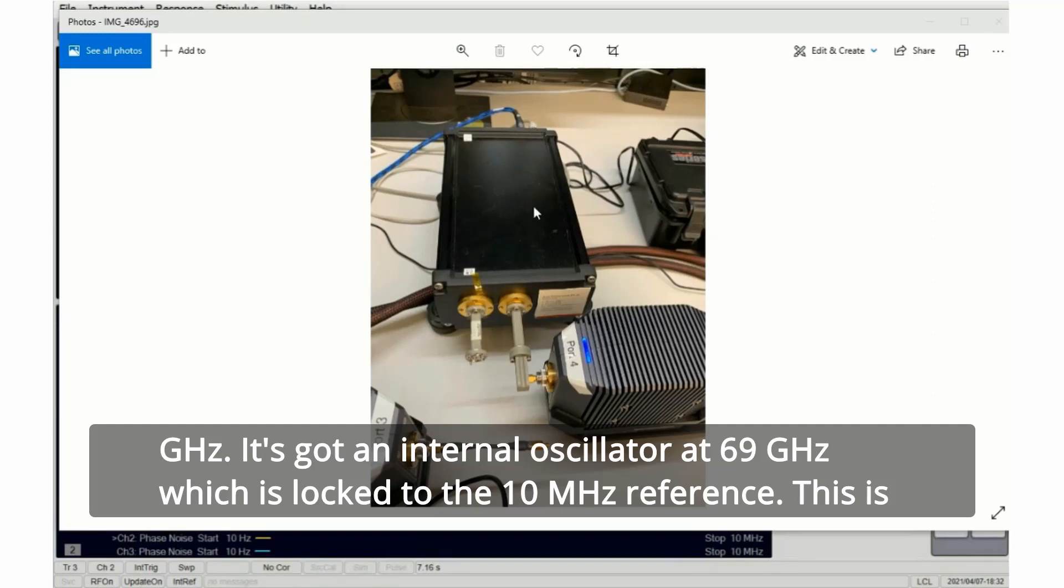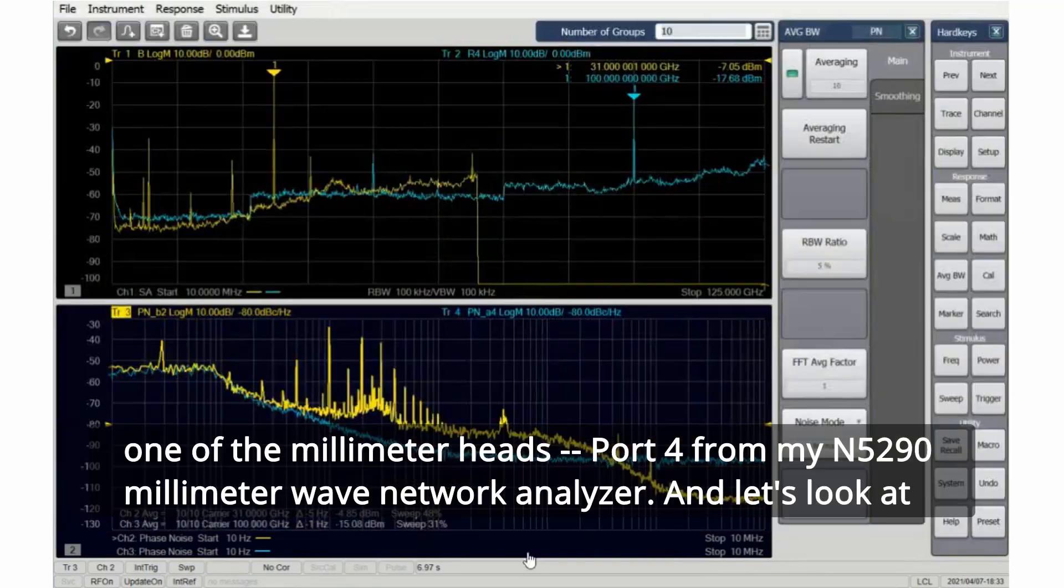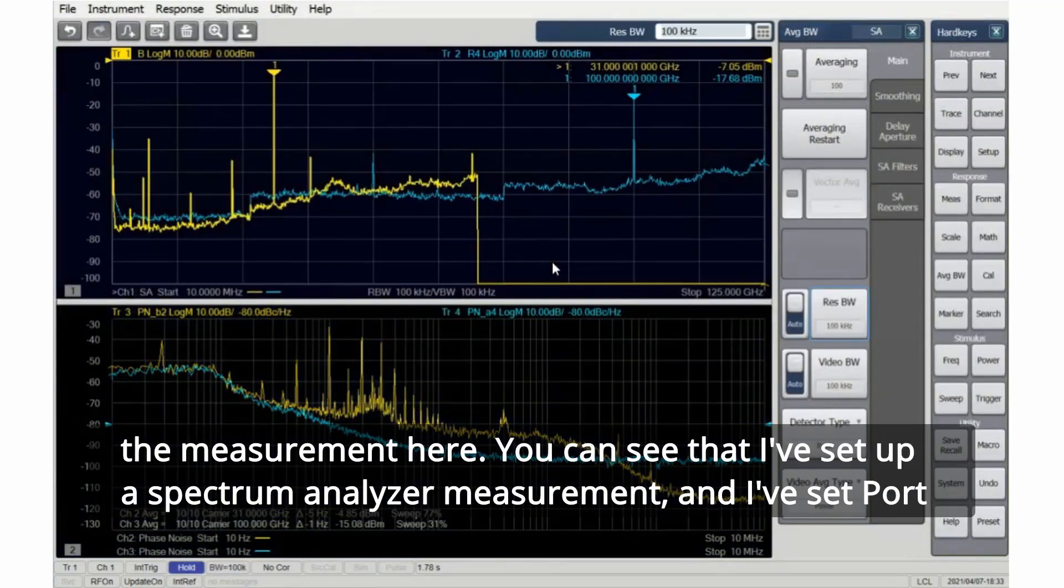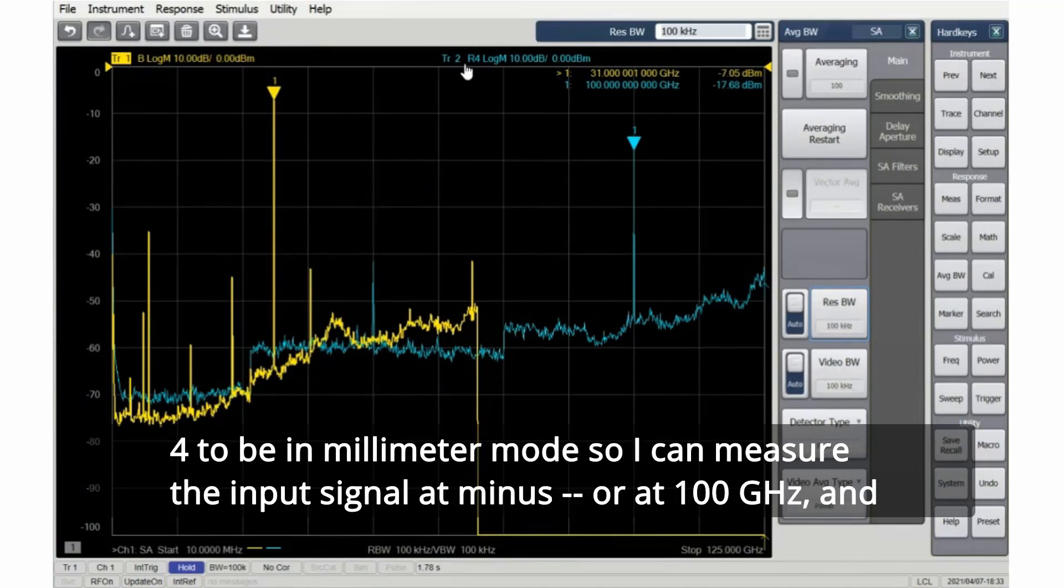This is one of the millimeter heads, port 4, from my N5290 millimeter wave network analyzer. Let's look at the measurement here. You can see that I've set up a spectrum analyzer measurement and I've set port 4 to be in millimeter mode so I can measure the input signal at 100 gigahertz.